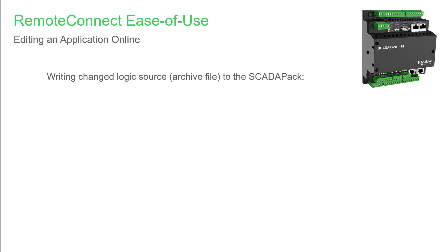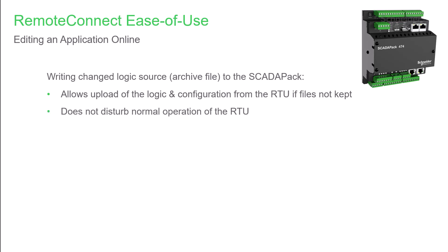To be able to upload an application from the SCADAPack to RemoteConnect in the future, you'll want to write the logic source updates to the RTU after online changes are done. This can be very helpful if the configuration files were accidentally not saved, or if you don't currently have access to them. Writing the logic source is an online action that does not disturb normal operation of the SCADAPack.